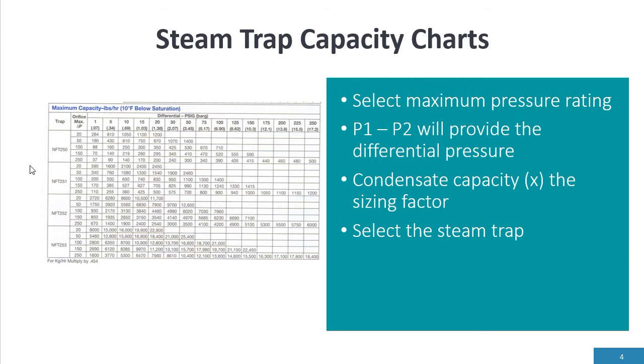Well, 1400 pounds per hour, if I go over to the left hand side, the orifice is only rated at 50 psi. We said we have to have the orifice rated for the maximum pressure, which is 150 psi. So if we come down 150 psi, 50 psi differential, the capacity is only 410 pounds per hour.